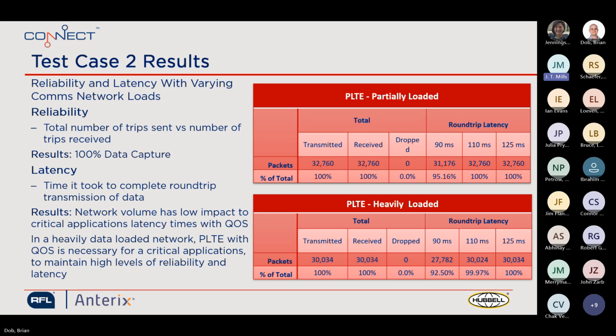During a heavily loaded scenario of a significant event, we were still able to capture 100% of the direct transfer trip signals. And as you can see in the latency, instead of the heavily loaded system being at 99.97% data capture at 110 milliseconds, at 125 milliseconds you would regain 100% data capture. But if you compare the 110 milliseconds in the two charts, you're only losing 0.03% of all data capture due to this heavily loaded event.